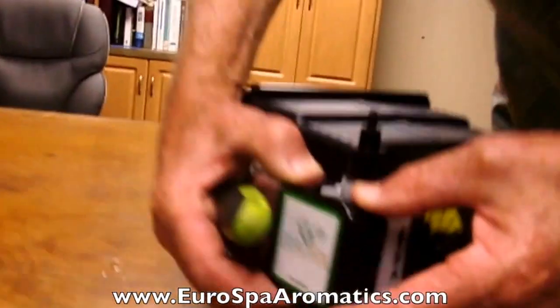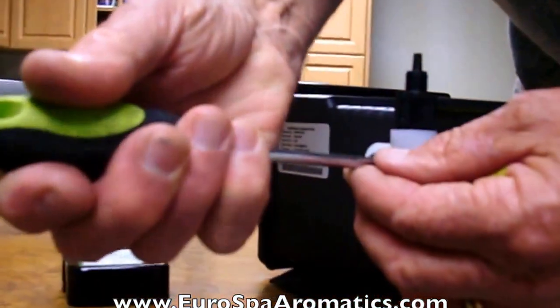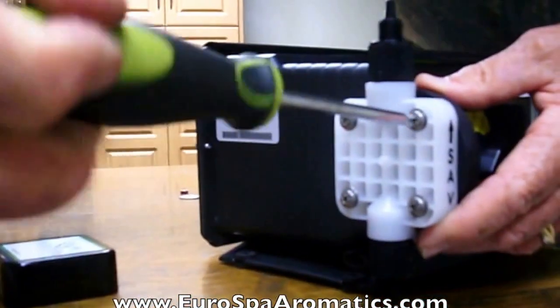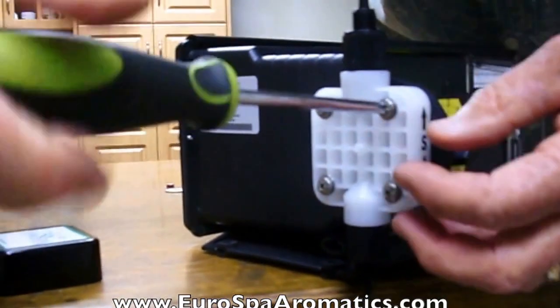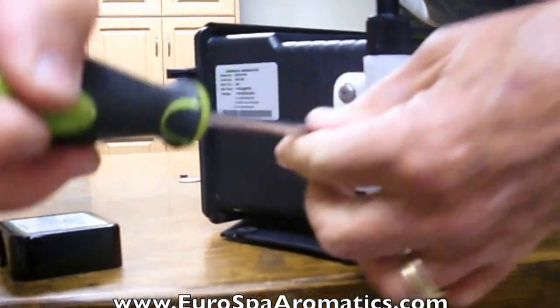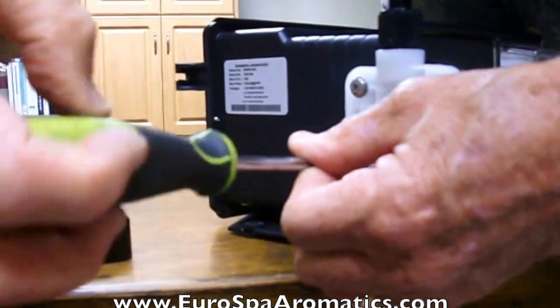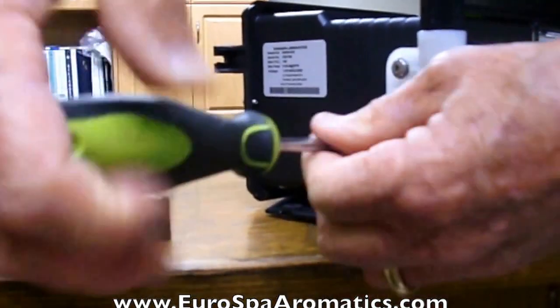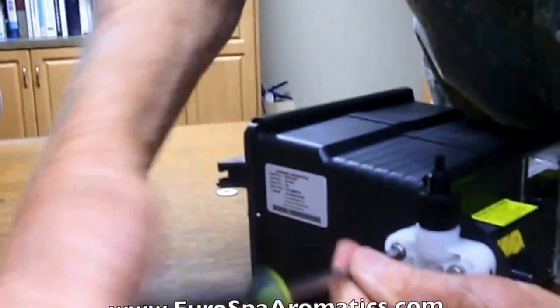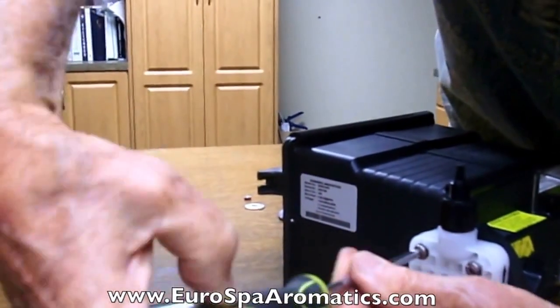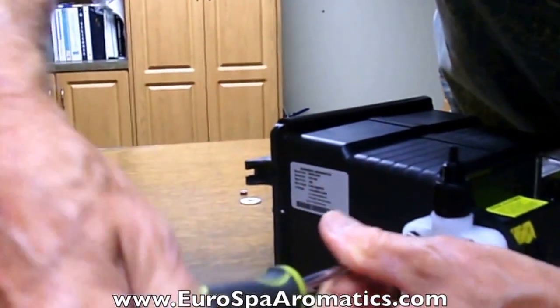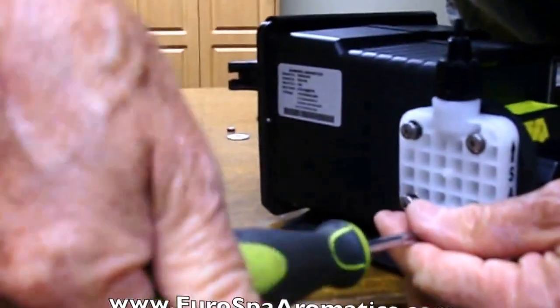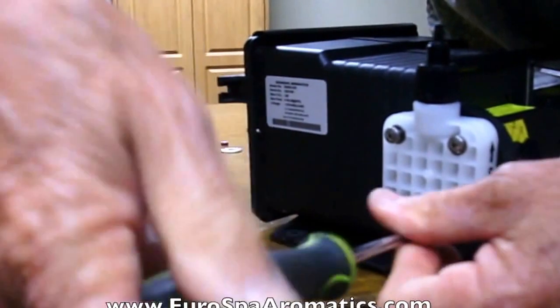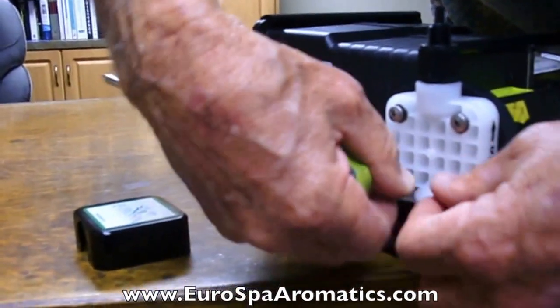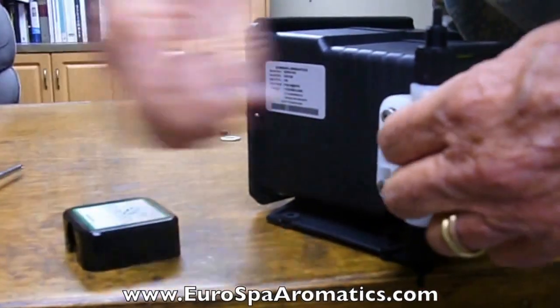Simply take off the protective housing from the pump head. There's 4 screws. Loosen all 4 screws, working your way around the pump head, going from opposite corner to opposite corner. As you loosen these screws, the pump head begins to back away from the pump housing itself. And once you feel that loss of torque, then you can go ahead and just back all 4 screws right out.